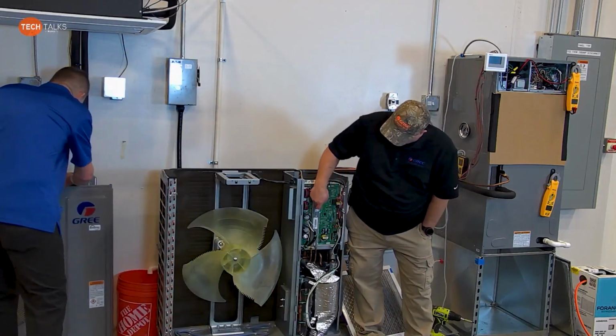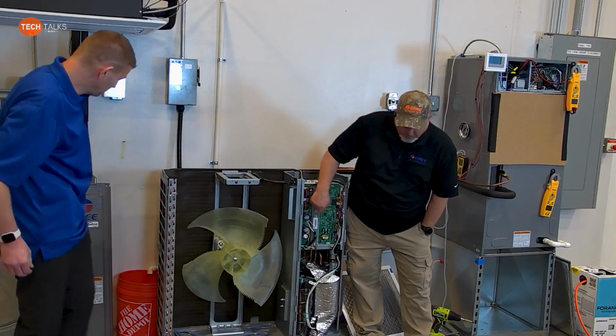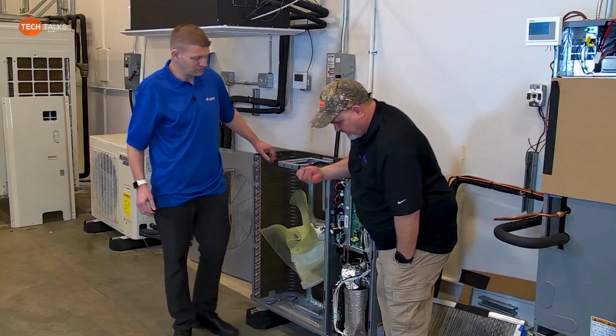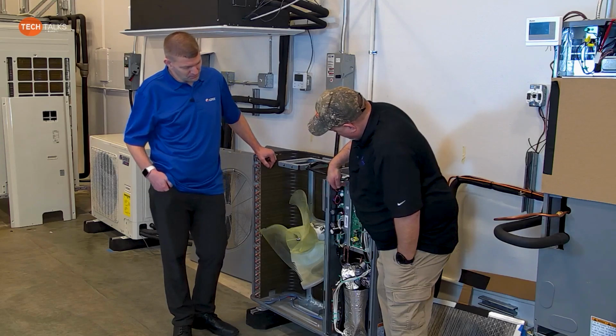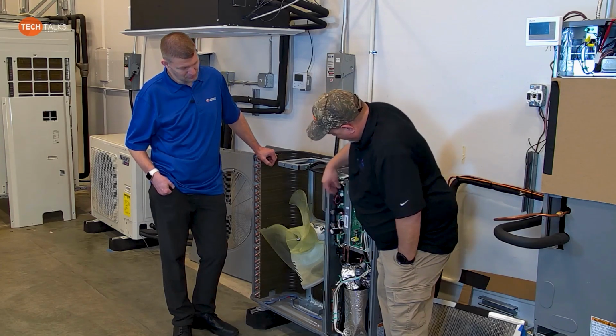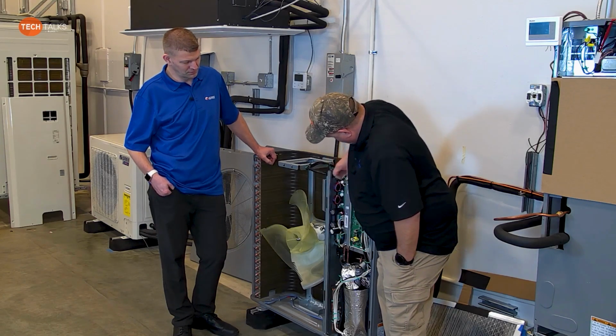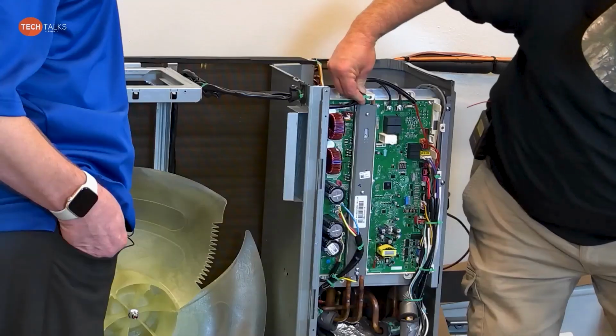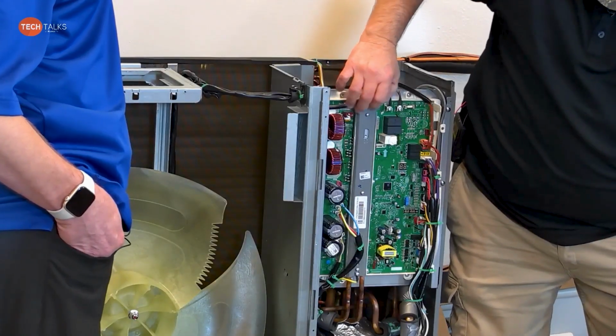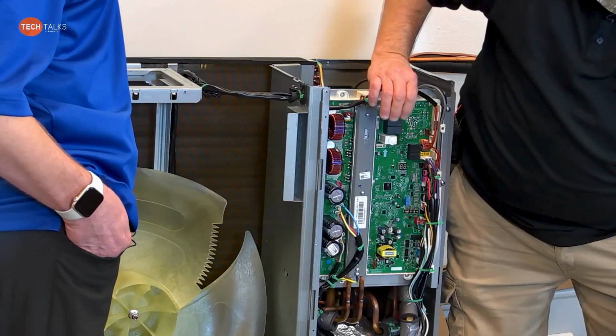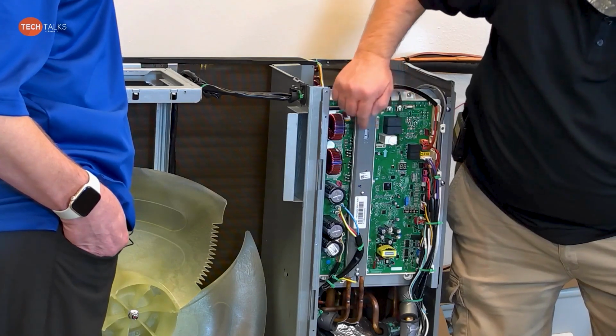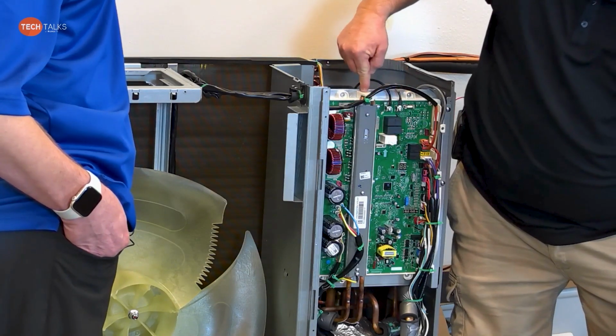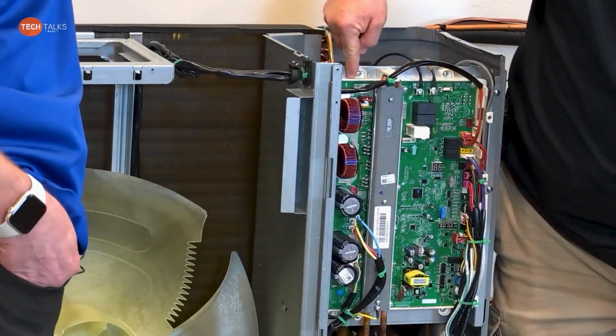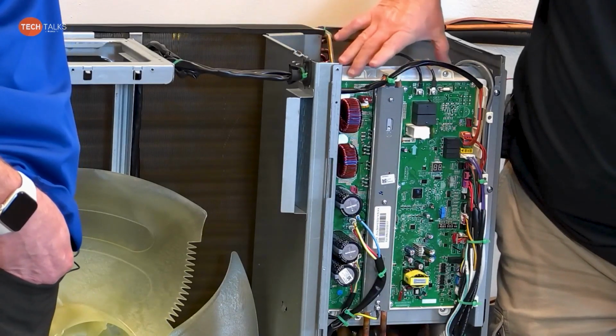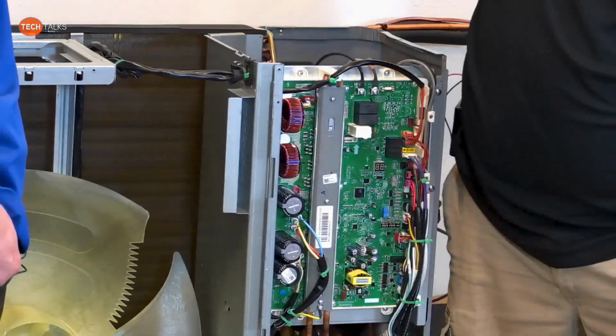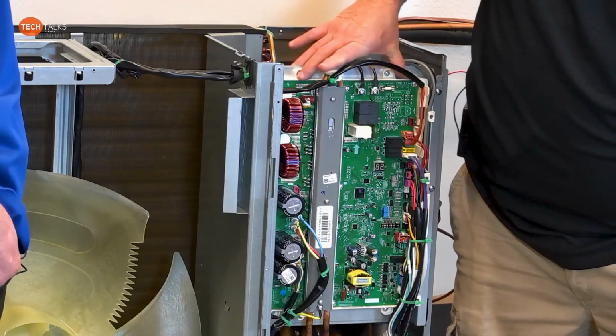So when you change this, and I don't want to do it because it's got all that thermal paste in there, it's messy, right? But if you undo these three screws, you can take this liquid line, and you probably have to get that zip tie out of the way, but you'll be able to pull that liquid line back just a little bit. Gently pull it back, and remember, when you change this board, you don't change the plastic. You're only going to get the board, but you can take the whole thing out, plastic and all, and then put it back, plastic and all.